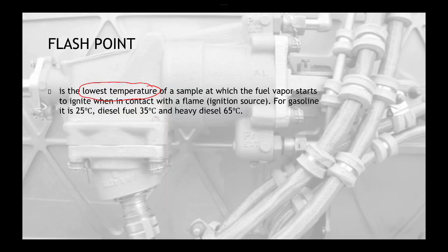In Tagalog po, ito po yung pinakamababang temperature na kapag sinilaban mo ay magliliyab. So flash point for gasoline is 25 degrees Celsius. For diesel, that's 35 degrees Celsius. And for heavy diesel, that's 65 degrees Celsius. That's the lowest temperature at which it will ignite when in contact with an ignition source.